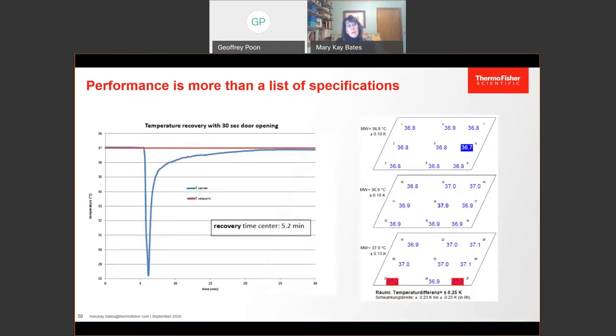When thinking about performance, remember that it's more than just a list of specifications. If you're looking at an incubator, for example, it's not just about what's the accuracy of the sensors, but how do those sensors perform in real life? What is the recovery after a door opening or what is the uniformity in that incubator? What's the deviation in temperature from the top shelf to the bottom shelf, for example? You should be able to have these sorts of data as well.